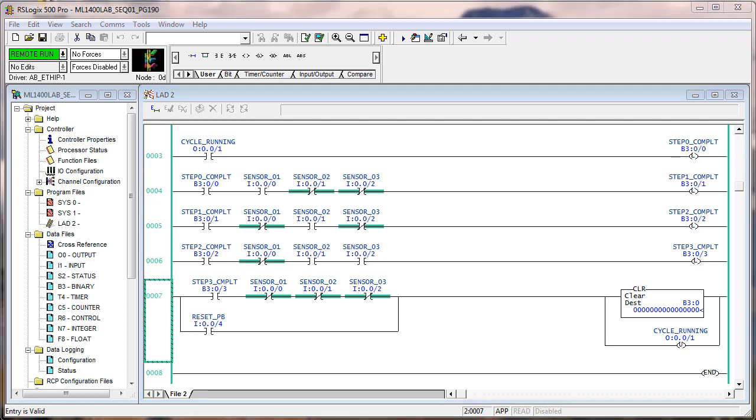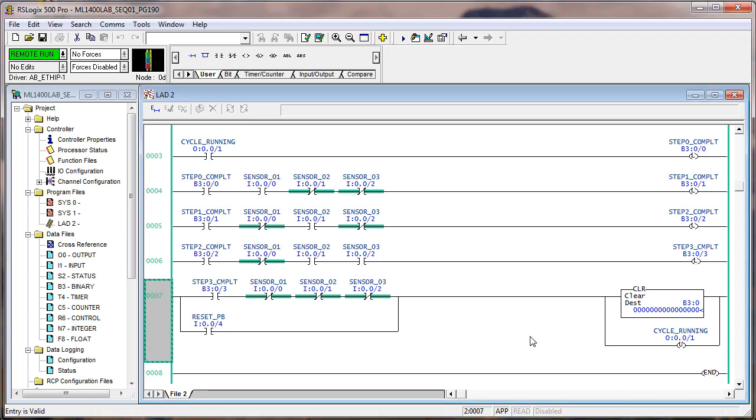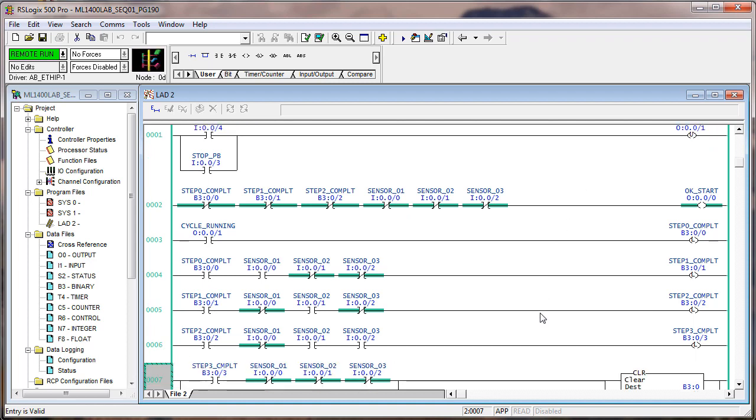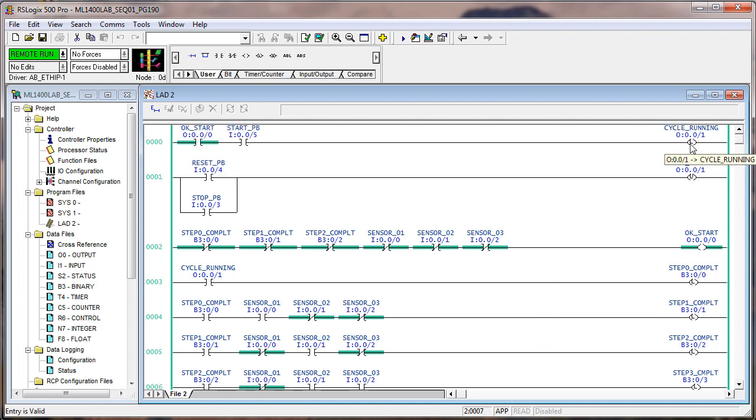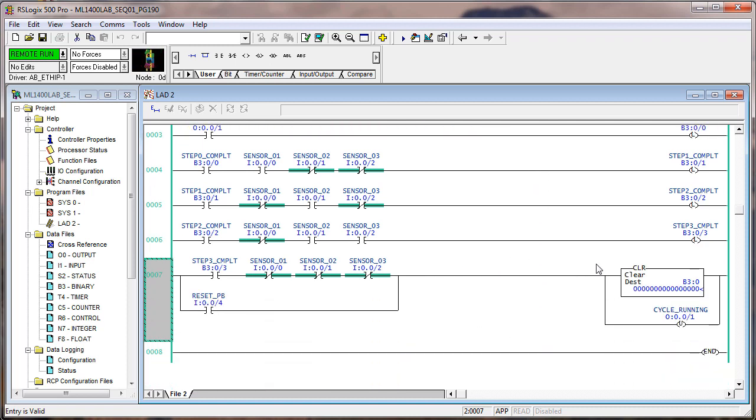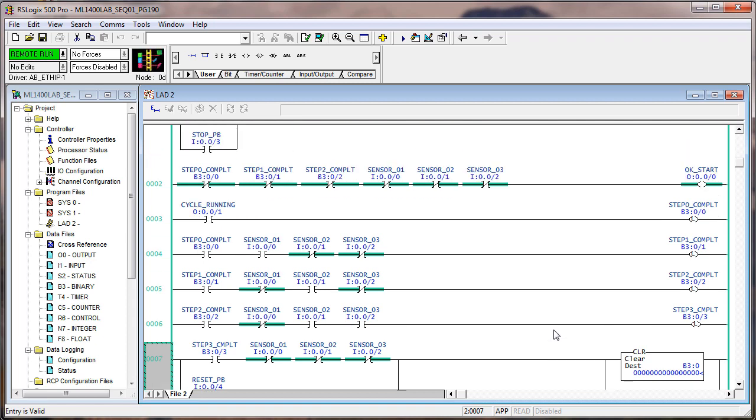I did have you shuffle your rungs around. In other words, right now these rungs are in a specific order. That makes sense logically to me in terms of reading the code. You want to get the cycle running. And we put the unlatch for cycle running right underneath of it, so it was easy to see what starts it and what stops it. Then we had okay to start. And then we went through our sequence. And then we cleared our steps. But you could rearrange any of these rungs in any order you like. It's still going to execute the same. So the answer to the question was: does the sequence still execute correctly? Yes it does. In other words, this logic is not scan dependent. If the rungs are executed in a different order, it's not going to affect the outcome.